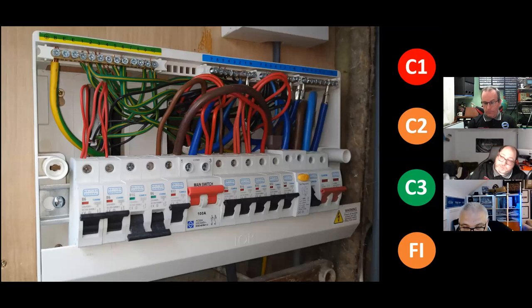Now, if the main fuse is an 80 amp, then that's three rings. But if the main fuse is 100 amp, that's not well balanced, is it? It's not protected against overload.